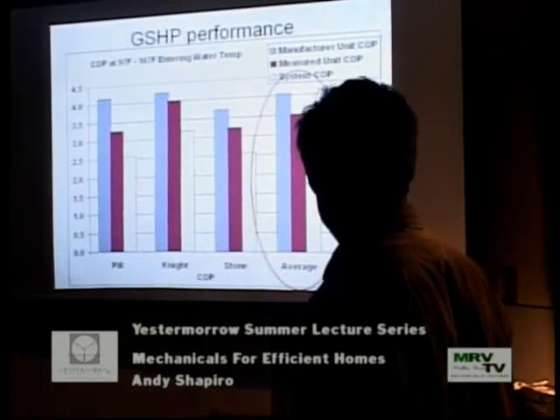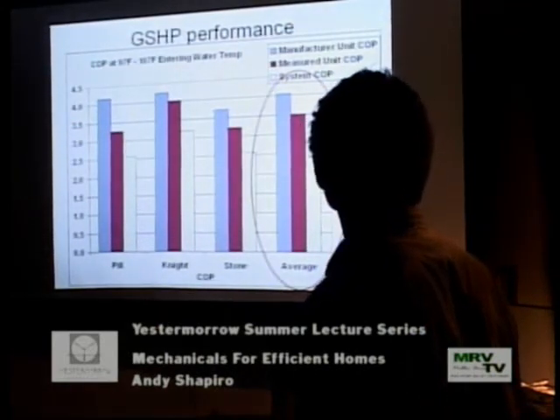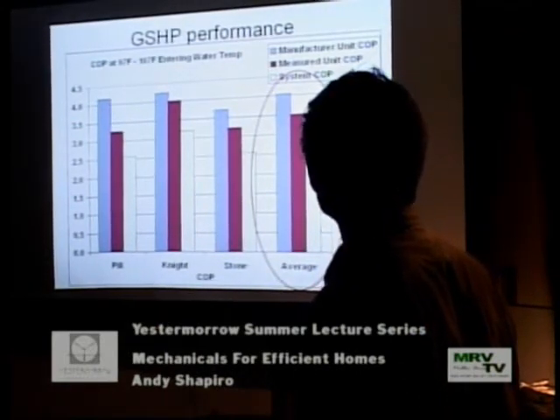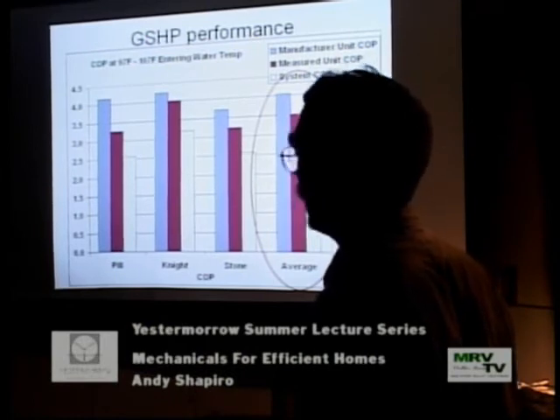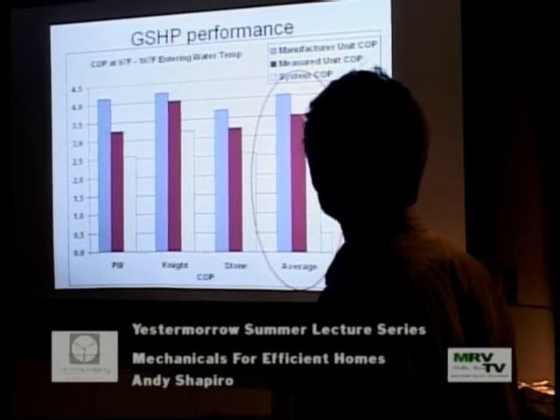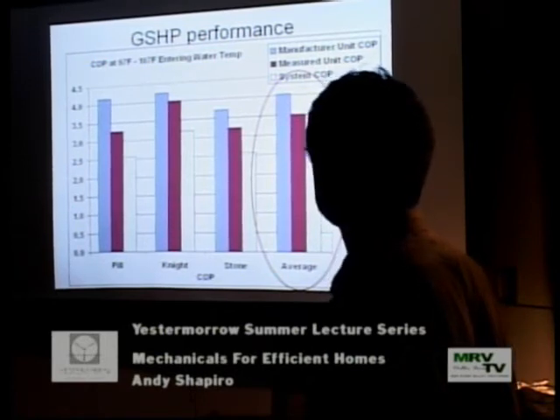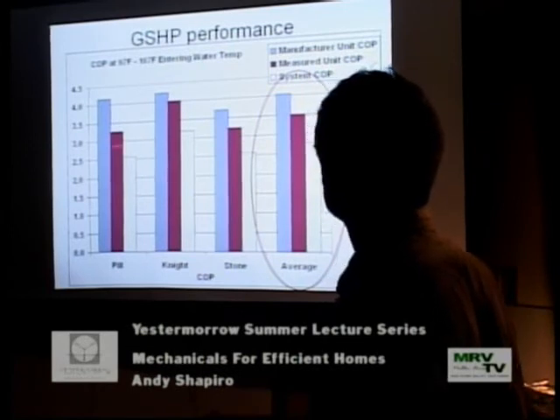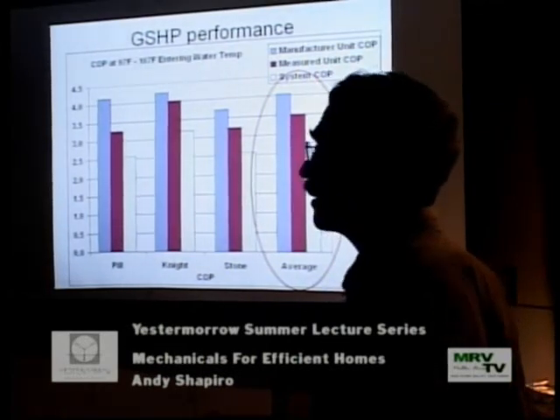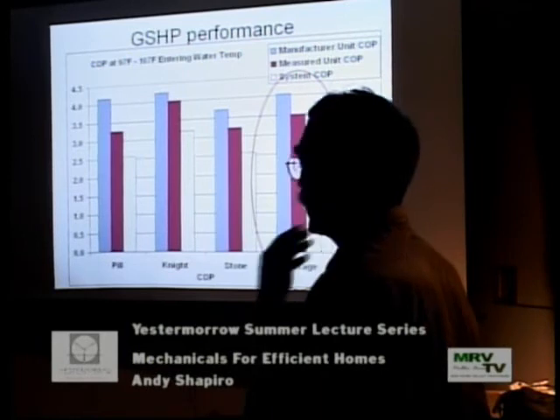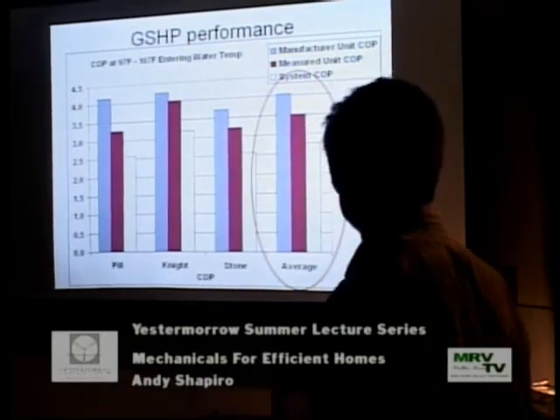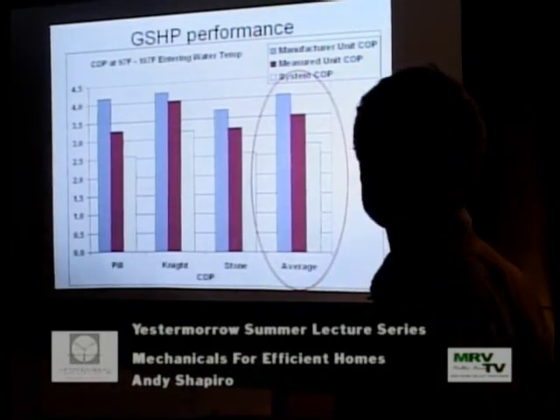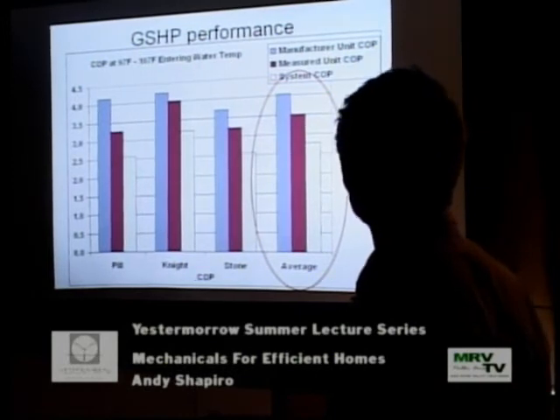So when you look at the manufacturer's rated COP for that box, it was 4. I measured the COP of the unit at 3.5. Okay, that's not bad. But if you take into account all the other electricity that's needed, the whole system is running less than 3 on average. You know, water-to-air heat pumps can be a little bit better than the water-to-water. So it isn't always this low.